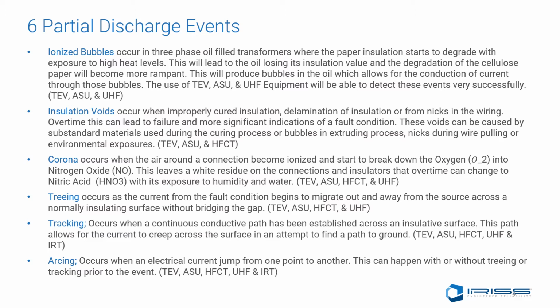Arcing occurs when electrical current jumps from one point to another. This can happen with or without treeing or tracking prior to the event. This too will also be detectable using TEV, ASU, and infrared technology. Sound analysis can also be a key determining cause of the exact fault condition that's present when looking for these 6 partial discharge events. They will each have a distinct pattern when viewed in software, and in a time signal analysis versus the frequency spectrum. These distinct images in conjunction with the PRPD screens and level modes allow the inspector the ability to make a decision about what steps to take next in the asset's health.